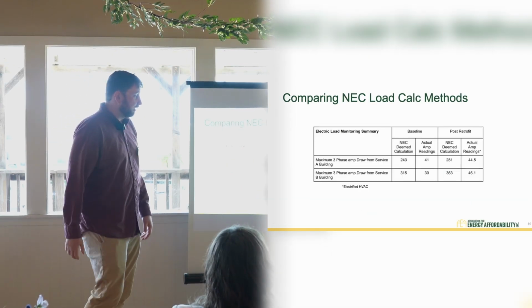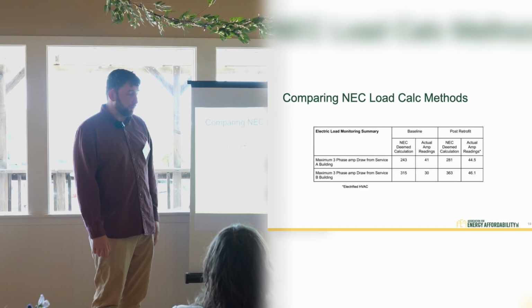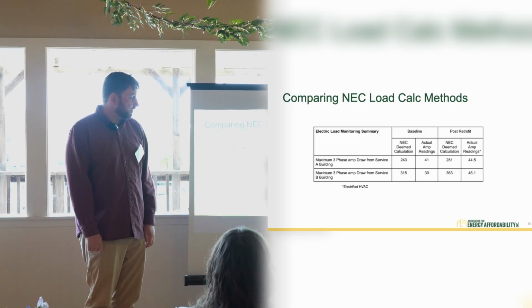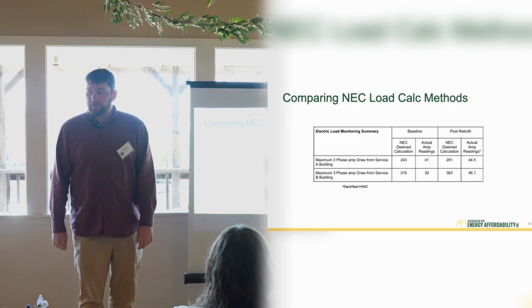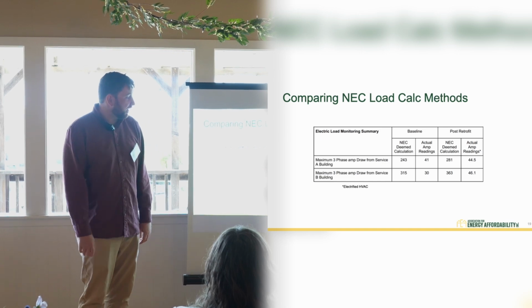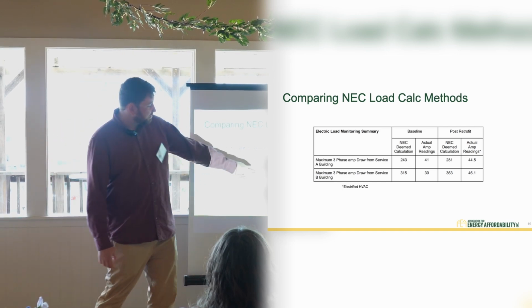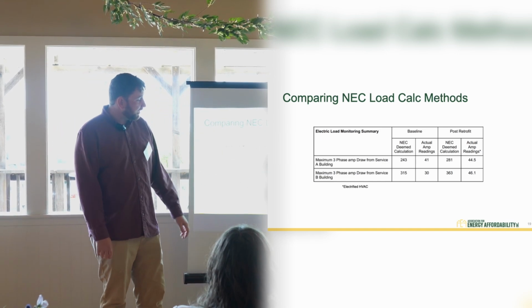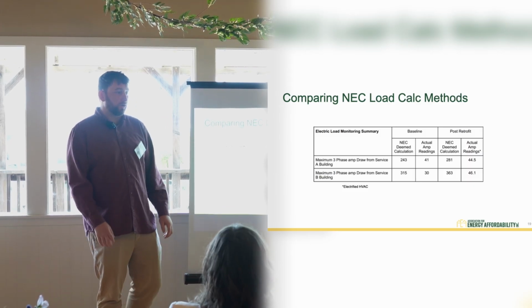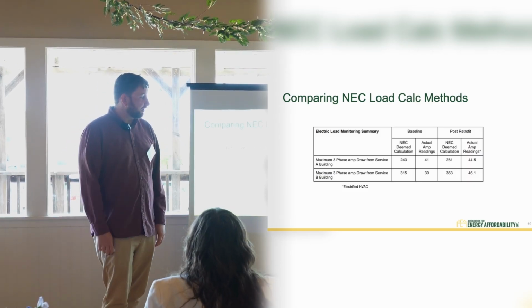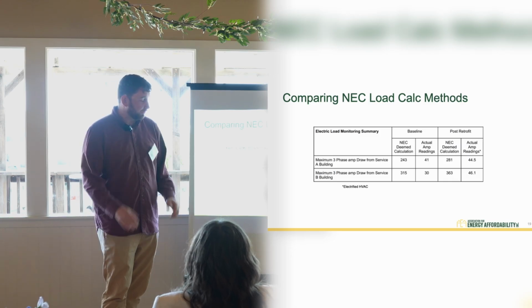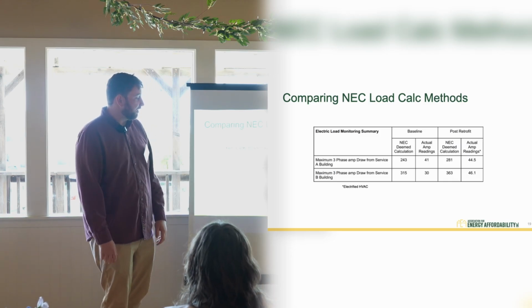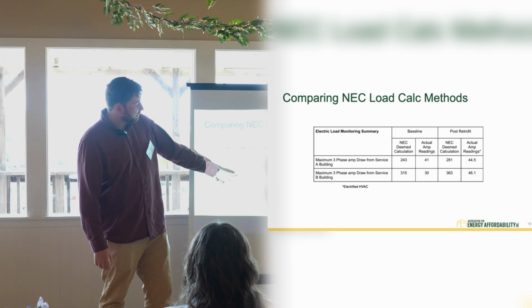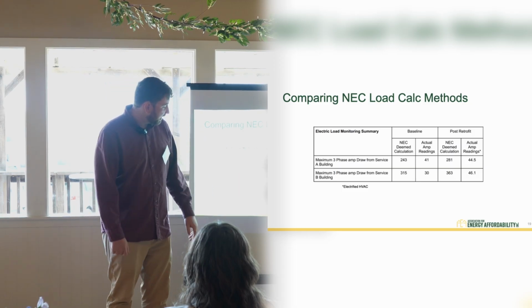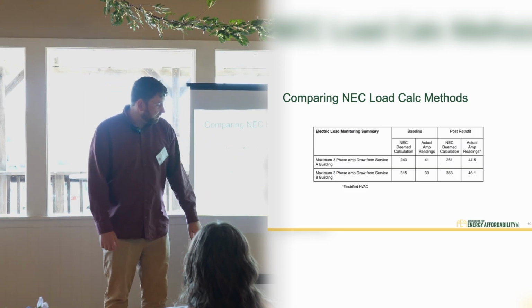Just to compare, this is a research project we worked on in Palo Alto where we installed mini splits in every unit. Each building was about 25 to 30 units. The first column here is the deemed calculation—what you get if you plug it into the electrical load calculator or National Electrical Code, following the code, adding up all the appliances and diversity factors. It tells us that we need 243 amps for building A, 315 amps for building B, and then we monitored.